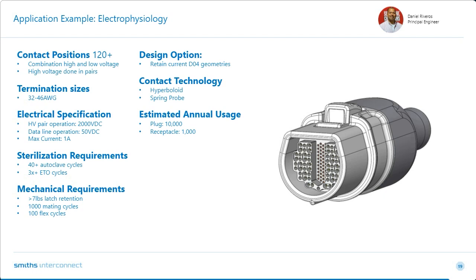We have high voltage pairs at 2000 volts and max current at 1 amp. Sterilization requirement was 40 autoclave cycles and 3 times ETO cycles. The mechanical requirements for this application are greater than 7 pounds latch retention, 1,000 mating cycles, and 100 flex cycles, flex being the cycles on the cable.